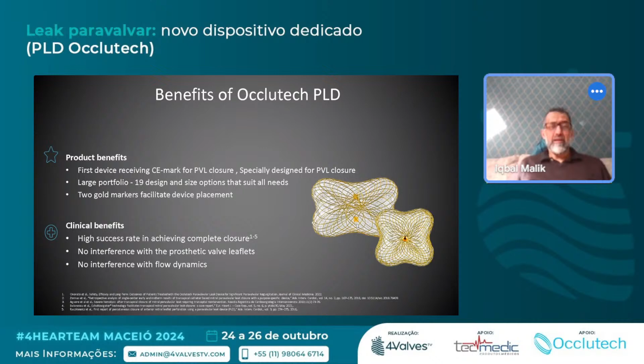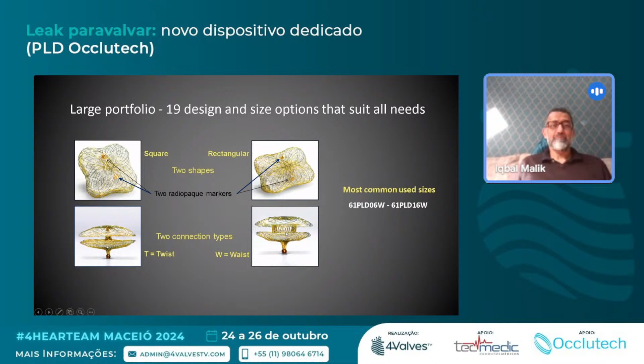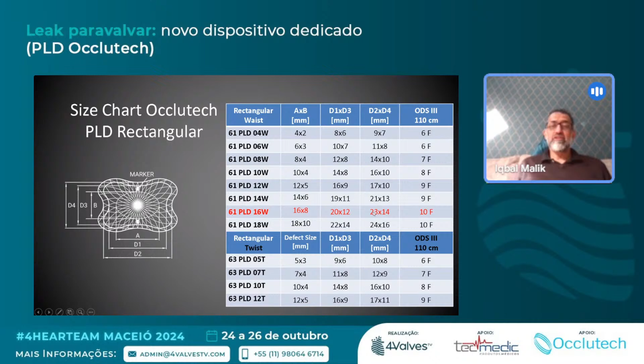So the large portfolio has either a square or a rectangular device, and either a twist waist or actually some bulk in the waist. I tend to use the ones with the bulk. I want to fill the leak with the device as well. The commonest ones that are used are the 6mm waist device. So the waist is 6, the discs are up to 11. And for the rectangular one, the 16 device, where the waist is 16 by 8 and the overhang you can see is nearly 2 centimeters. But that does require quite a big sheath to actually go through.